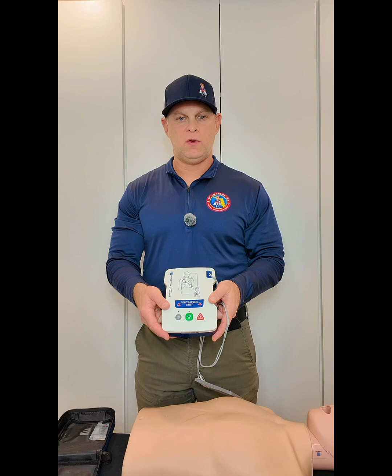Once you manually power the device on, you will begin to receive audible prompts. Adult patient. If the patient is a child, press the child button. The first audible prompt that I received from the trainer device is it informing me that it is defaulted to adult mode. If you have a child victim, some devices do have the capability to be changed to child mode. Locate the child mode button, press it down, and activate child mode. Once in child mode, the device will lessen the energy that is delivered with the defibrillation based on the smaller size of the patient.